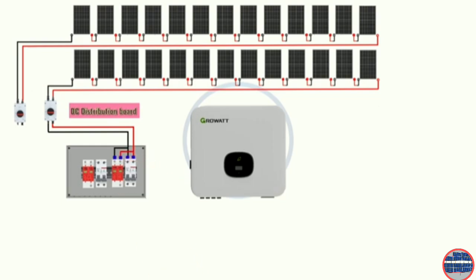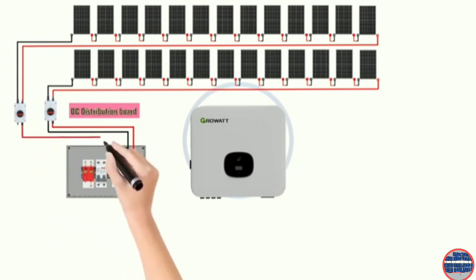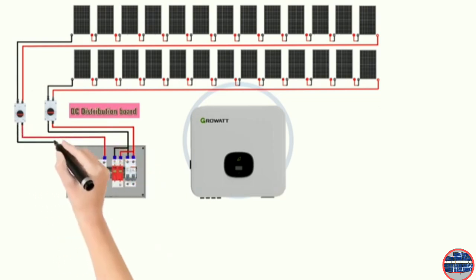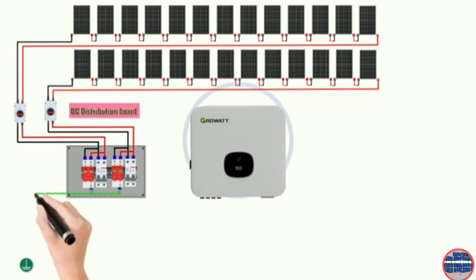SPD connection parallel to MCB. Positive connection: connect a wire from the positive output terminal of the MCB to the positive terminal of the SPD. Negative connection: connect a wire from the negative output terminal of the MCB to the negative terminal of the SPD. If the SPD has a common negative, connect it to the negative output of the MCB. Earth connection: connect the earth terminal of the SPD to the grounding system, earth bar or designated grounding point.